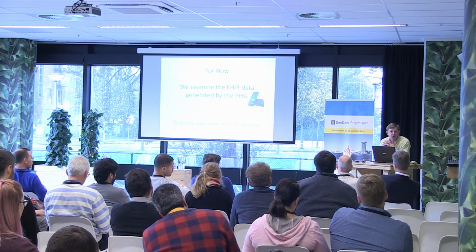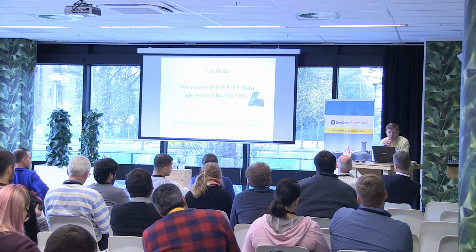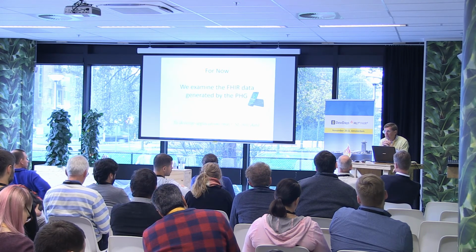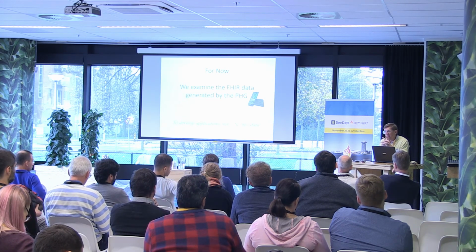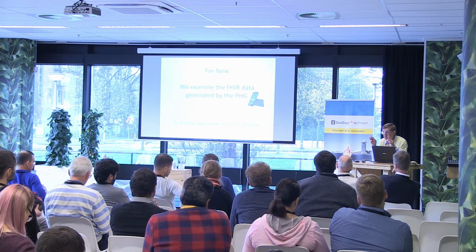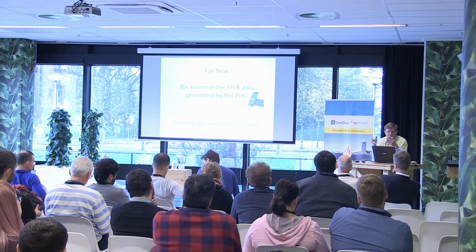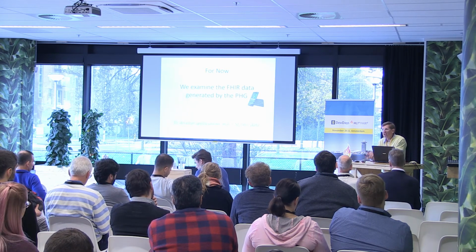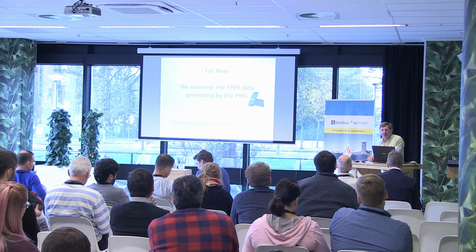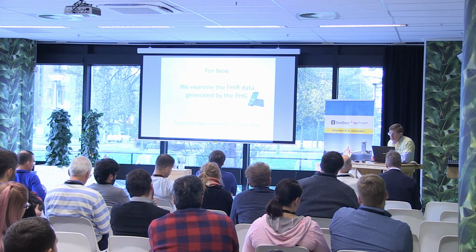The unit is also an MDC code, but we map them to UCUM, so what's displayed in FHIR is UCUM. However, the implementation guide says specifically, to be future-proof, that if you don't know the UCUM code for the MDC code, use the MDC code, because the PHG will always know the MDC code since the device provides it. It does not provide UCUM. That's too inefficient. These are binary.